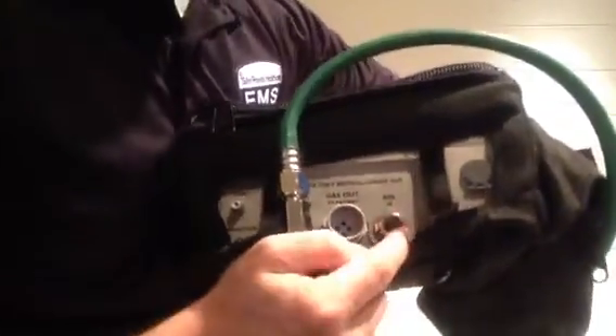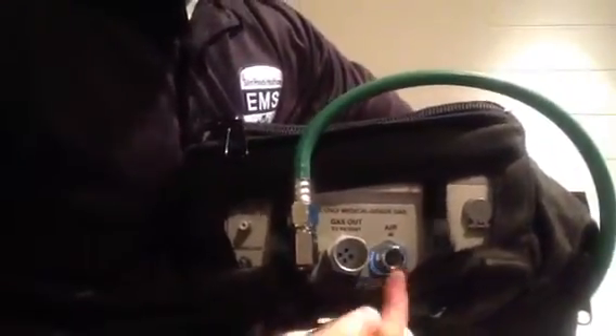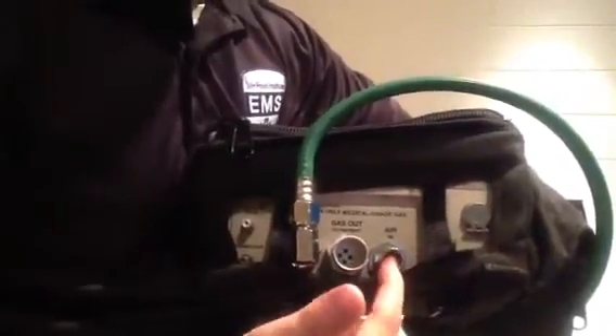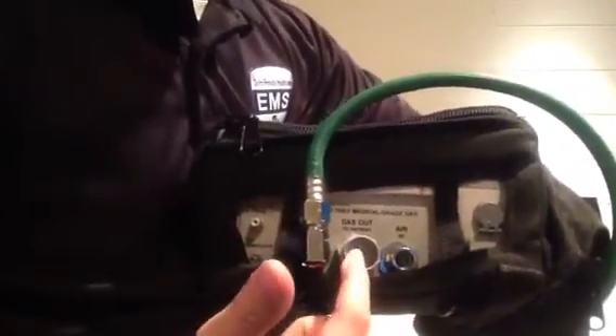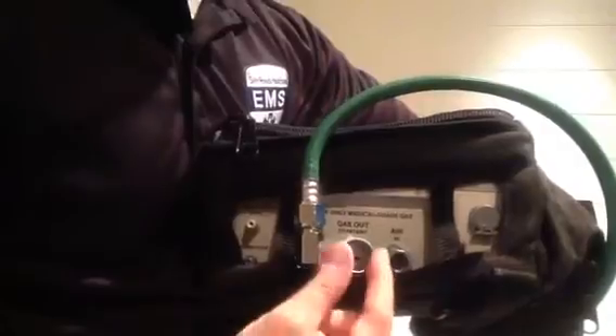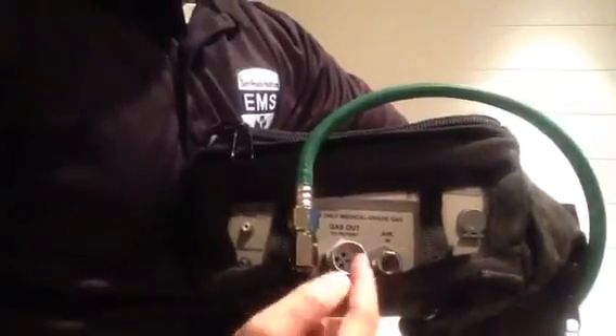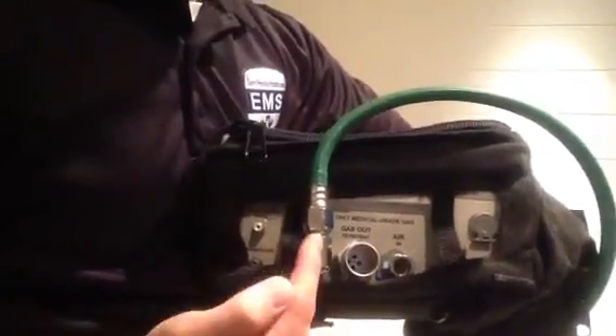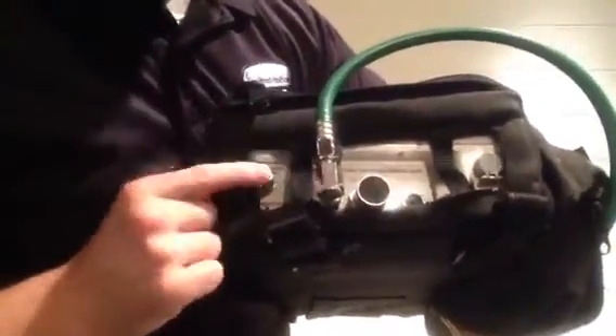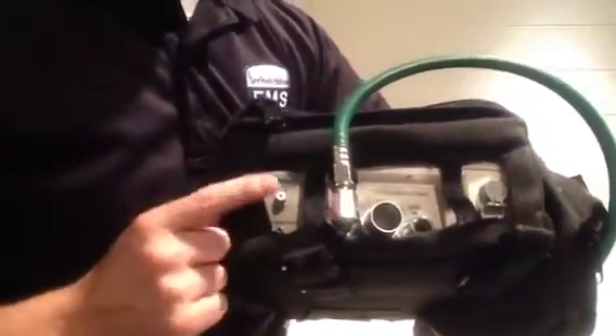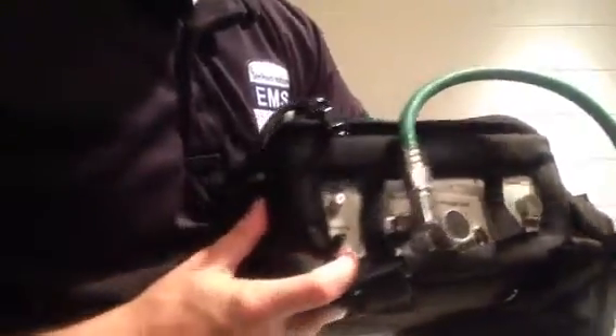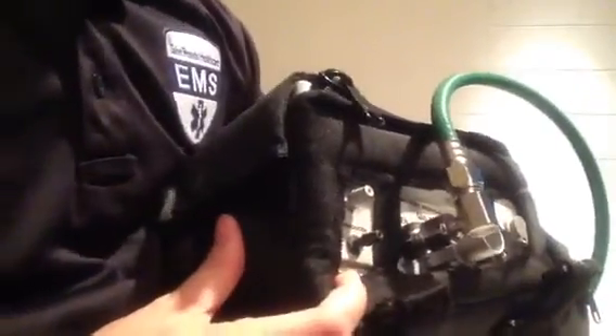So just to review, we've got our power line, our bleed in for various air products, if you were going to bleed helium into your line or whatnot. This is your exhaust line for actual out to the patient. This would connect to your regular vent circuitry. Your 50 psi for oxygen, and then you have your exhalation valve and your transducer. You notice this one's silver colored. This one actually has a color to it, and that's going to come in handy for us in just a second.